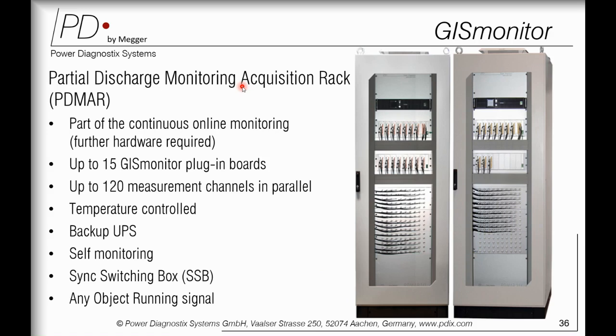And this is the online PDMR, which is used on GIS monitoring. It is a solution for continuous monitoring of PD, and a part of continuous online monitoring. It has 15 inbuilt GIS plugin boards, and each plugin board has 8 channels. So it gives you up to 120 measurements with one single monitoring acquisition rack. It is completely temperature controlled, backed up with UPS, and self-monitoring. That means you don't need manpower to sit in front of it; it is a completely manless situation. That's why it is also a great tool for digital substations. We have a sync switching box, and everything is monitored in this acquisition rack.